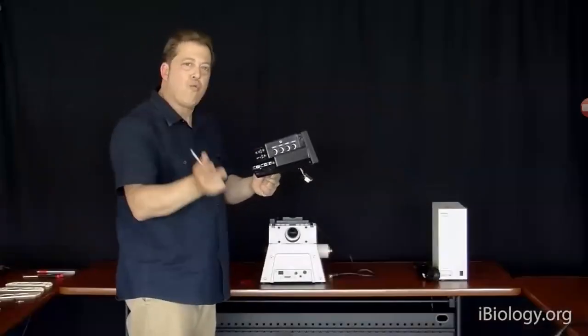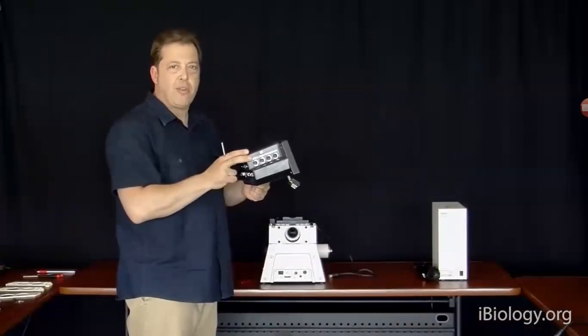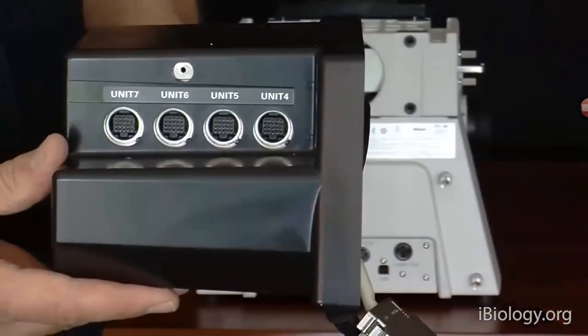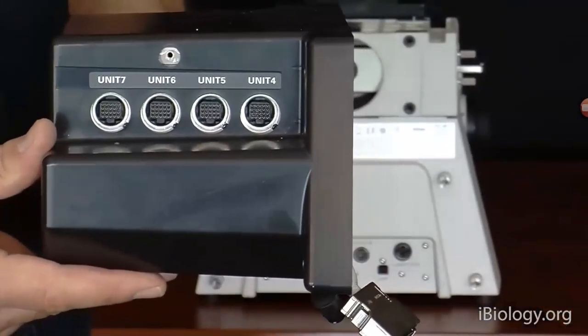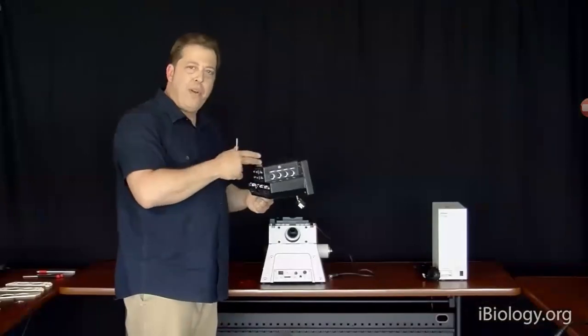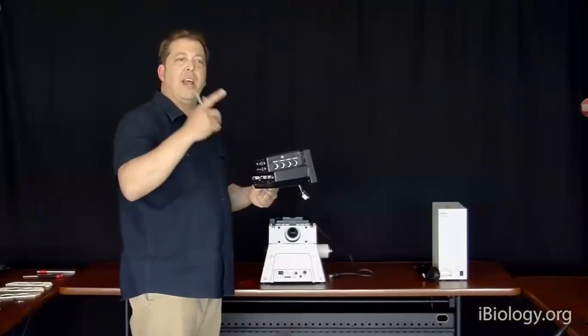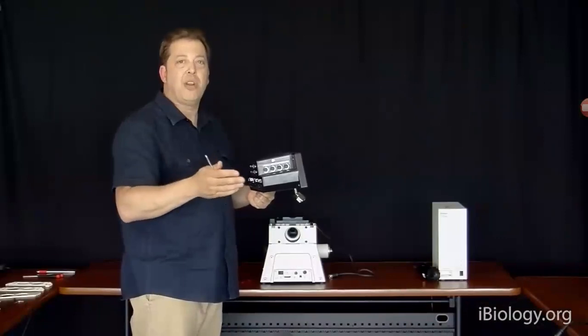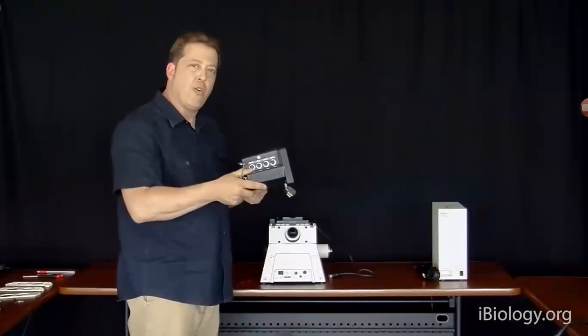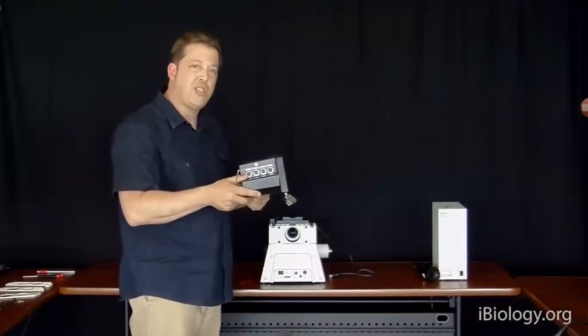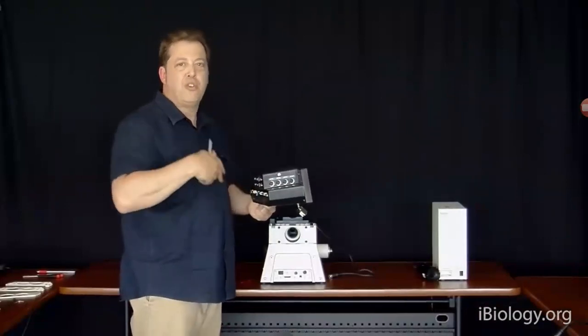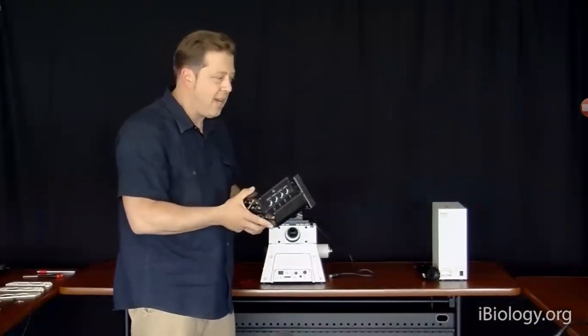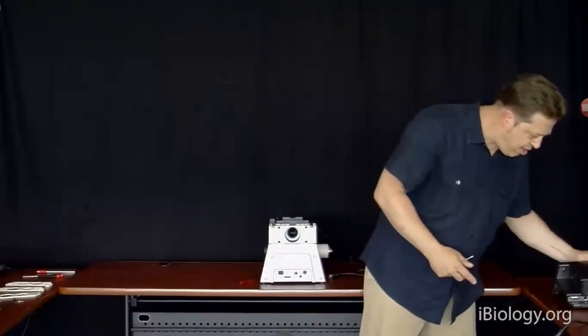And the hub controller then runs all the electronics on the microscope locally, rather than communicating back and forth with the computer saying, open a shutter. Okay, the shutter's open. That type of communication could take a long time. By doing it all locally, we can actually achieve much higher speeds on the microscope to do different imaging sequences. So we'll place this here. Okay.